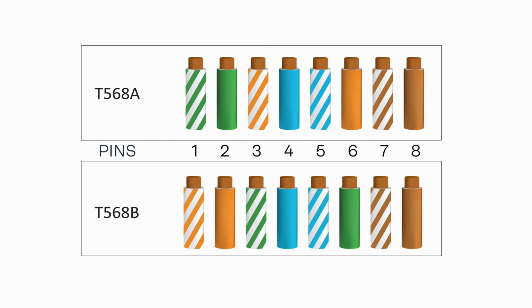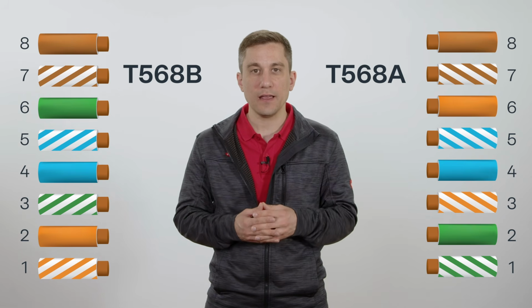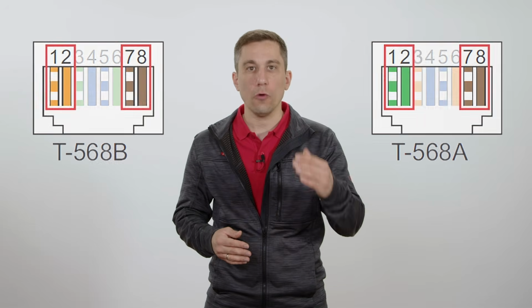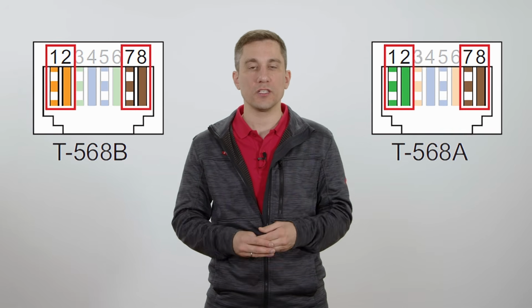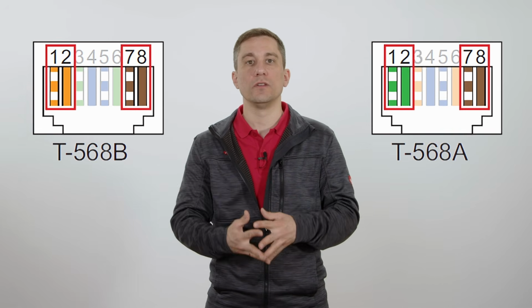Please always note whenever you cut open the cable on the inverter side, of course you need to watch which version, variant A or B, is being used on the RJ45 plug so that you have the color coding on the cable correct. For our internal application at Fronius, we always need to have the correct pins installed on the inverter, in correlation to the battery system. So this is very crucial because otherwise, when the color coding is not correct, the data communication will not work. So please always keep that in mind when installing.